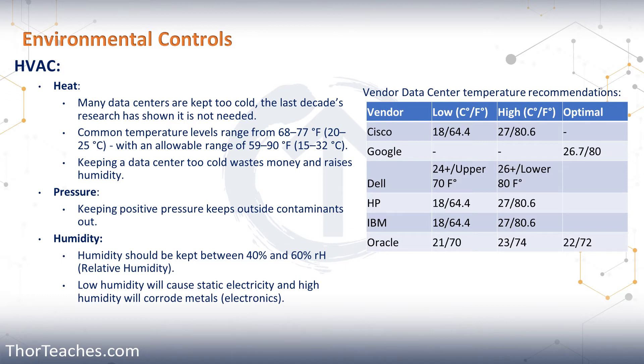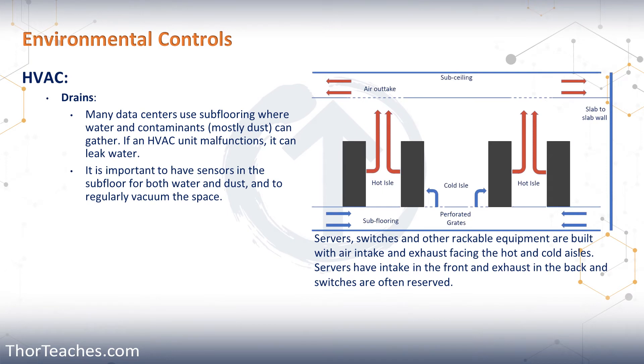We need to ensure that we operate in the optimal range. I have worked in data centers where it is both really, really dry and others where it's really, really humid. In Central California, where it was 115 Fahrenheit in the summer or 45 Celsius, we needed to use the humidifier because the relative humidity in the air we pulled in was too low. When I worked on Oahu in Hawaii, we needed to pull humidity out of the air. We've already touched on how important it is to have enough HVAC redundancy so if one unit goes out, we have another that can carry the whole load. While this is not specifically your responsibility, you need to understand exactly how it works so you can ask the right questions to ensure we have the right protection.